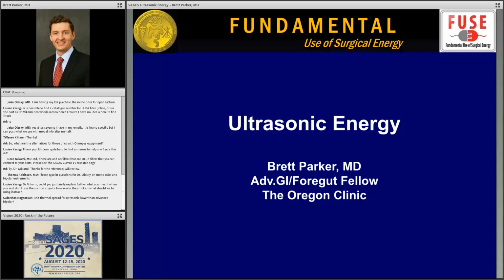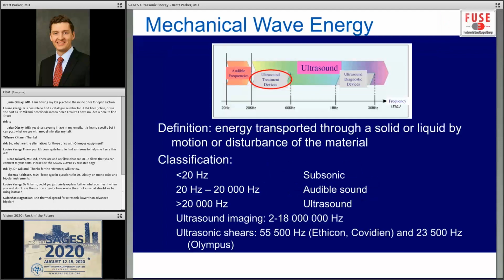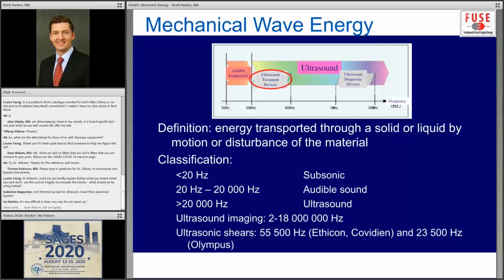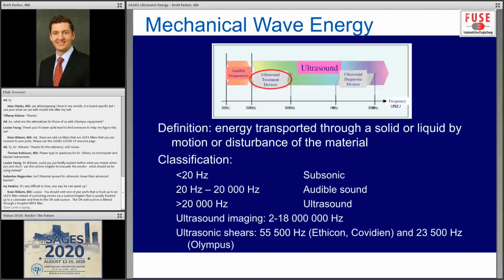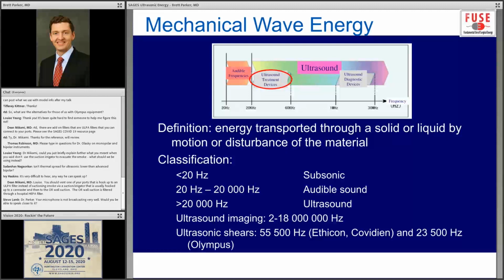So we'll start now. Ultrasonic energy is a type of mechanical wave, and this definition is the energy is transported through a solid or liquid by motion or disturbance of the material. It's classified on this spectrum of frequencies that you can see here on slide 1. On the far left, less than 20 hertz, which is vibrations per second, you have what's known as subsonic energy, and this is energy that you can feel. Between 20 and 20,000 hertz, or the orange area here, you have frequencies that you can hear. So you have audible frequencies, and then moving up the spectrum over 20,000 hertz, you have ultrasound, and that's signified here with the red signal, and will be the primary frequency for the devices we discussed today.